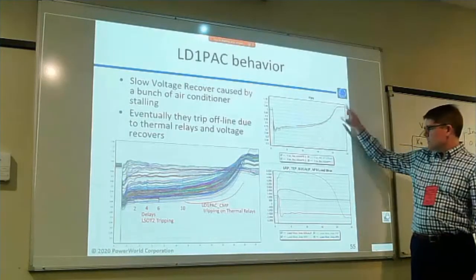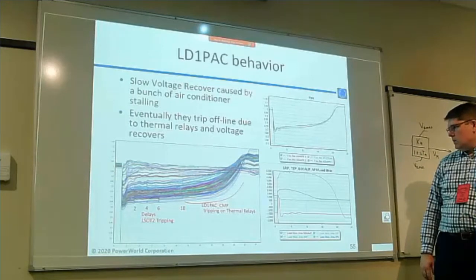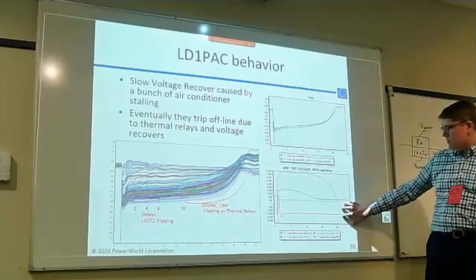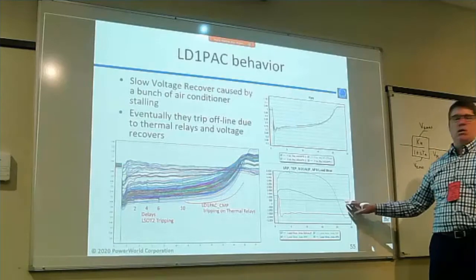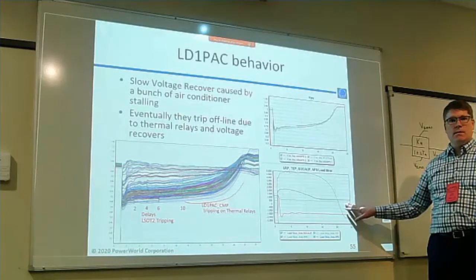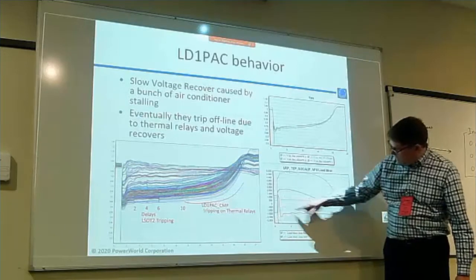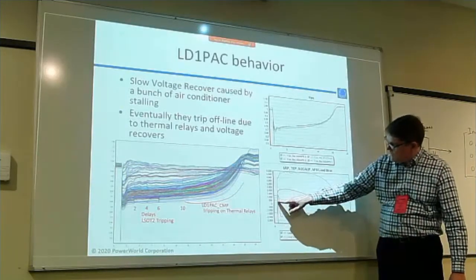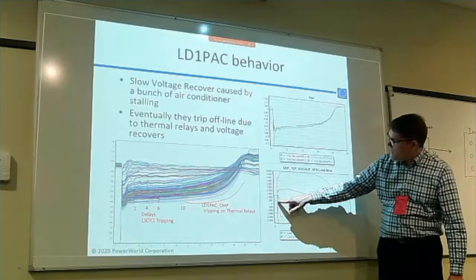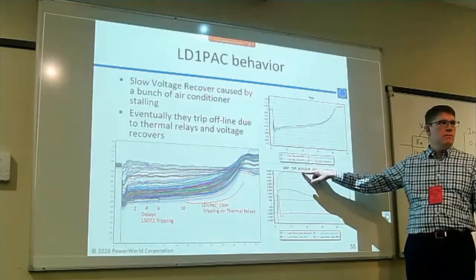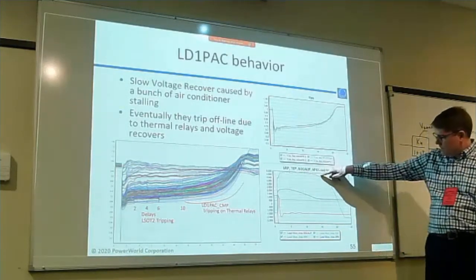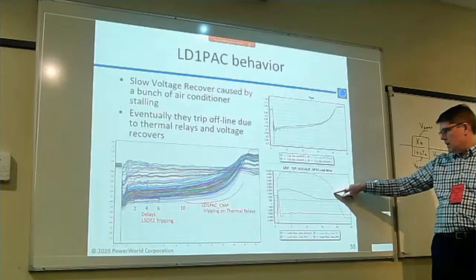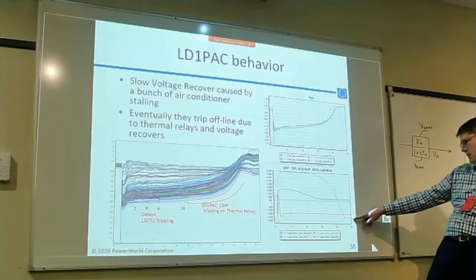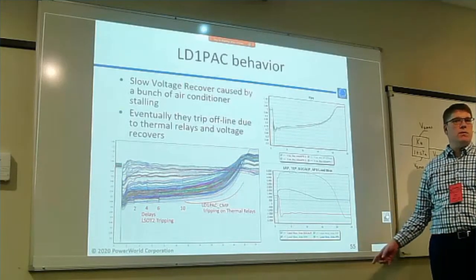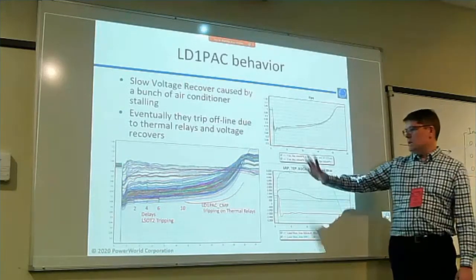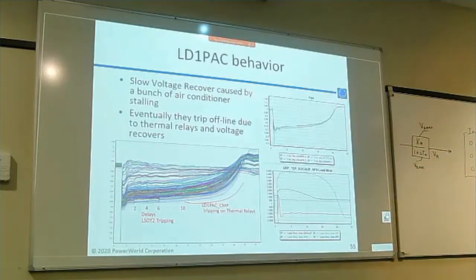And so yeah, here's the kind of classic response. This is a good picture. This is showing the megavar loads in those areas. They start out here, and in particular, look at SRP. It starts at 500. The megavar loads go up to 6,000. They hang out there for 15 seconds, and then eventually come back down to minus 1,500 because a whole bunch of loads tripped. So this is the kind of behavior that you'll see with this model.